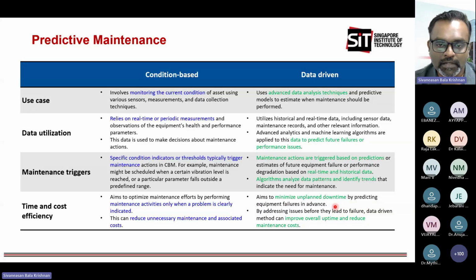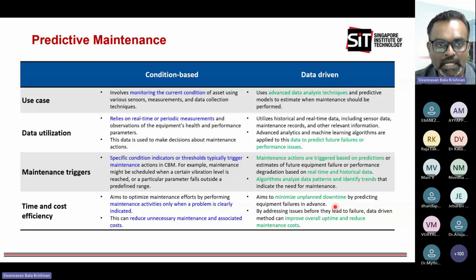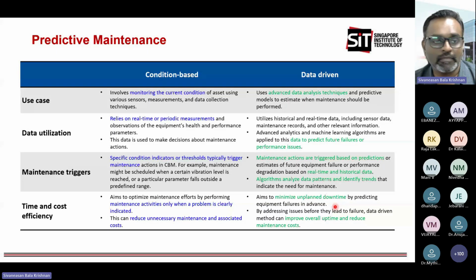We rely on real-time or periodic measurement of parameters, measured continuously or every half hour or hour. In an electrical system, we measure temperature, partial discharge, pressure, or vibration data. This data helps identify if the asset's condition deviates from normal operation, compared against some threshold.